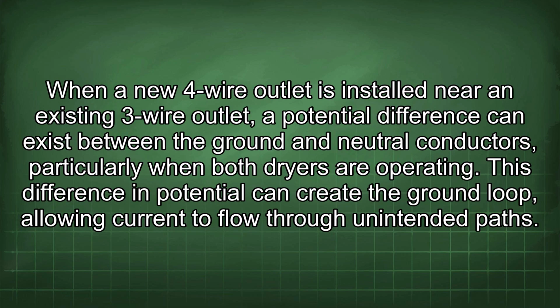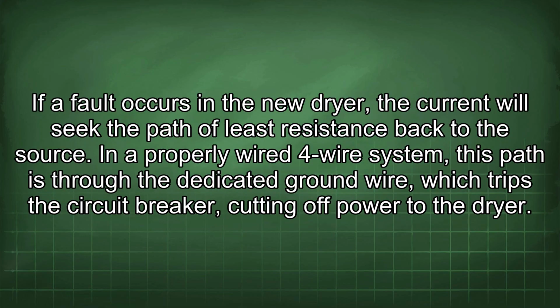When a new 4-wire outlet is installed near an existing 3-wire outlet, a potential difference can exist between the ground and neutral conductors, particularly when both dryers are operating. This difference in potential can create the ground loop, allowing current to flow through unintended paths. If a fault occurs in the new dryer, the current will seek the path of least resistance back to the source. In a properly wired 4-wire system, this path is through the dedicated ground wire, which trips the circuit breaker, cutting off power to the dryer.